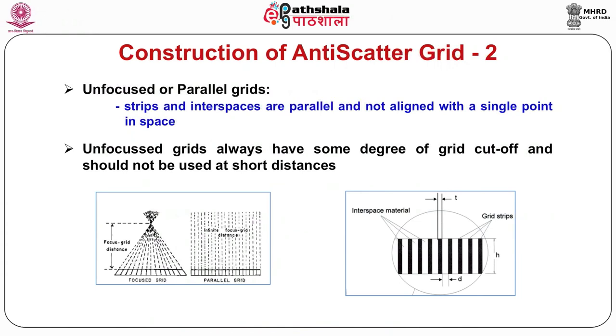Typical grid focal lengths are 100 cm for general radiography and 183 cm for chest radiography. In an unfocused or parallel grid, the interspaces and strips are parallel and are not aligned with a single point in space. Because the X-ray beam direction is aligned with the grid, much of the primary radiation passes through the interspaces without encountering the lead strips. The scattered radiation leaves the patient's body in a direction different from the primary beam, and hence a large portion of it is absorbed by the grid. Unfocused grids always have some degree of grid cutoff and should not be used at short distances.